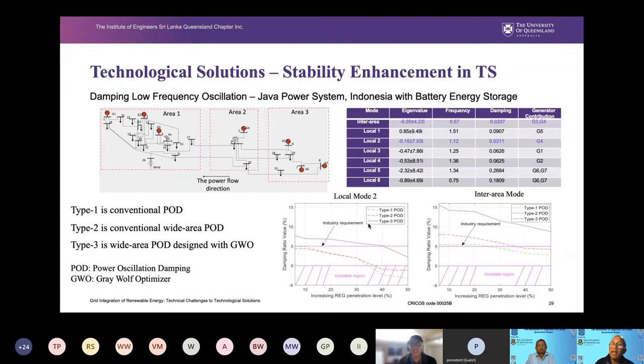When it comes to the industrial standard, we are looking at 5% or more in the damping. When we have this controller, the battery energy storage and the appropriate tuning, we can achieve 15% of damping. And definitely, this 15% reduces as we grow with renewable energy. Looking at the local mode, we can accommodate up to 40% renewable energy and still achieve 5% damping. For the inter-area mode, which is considered the problematic one, we can achieve over 50% renewable without having this problem.